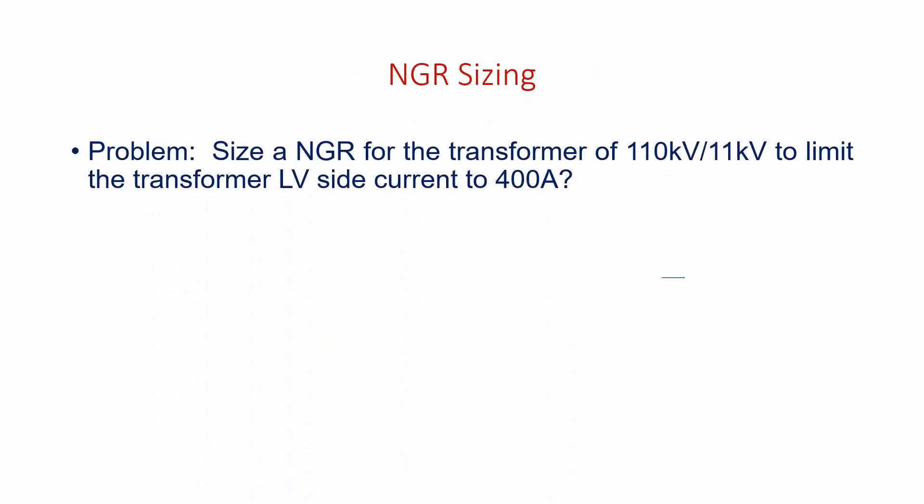Then NGR sizing - how to size NGR? Let's have a simple problem: Size an NGR for a transformer of 110 kV / 11 kV to limit the transformer LV side single line to ground fault current to 400 amps.